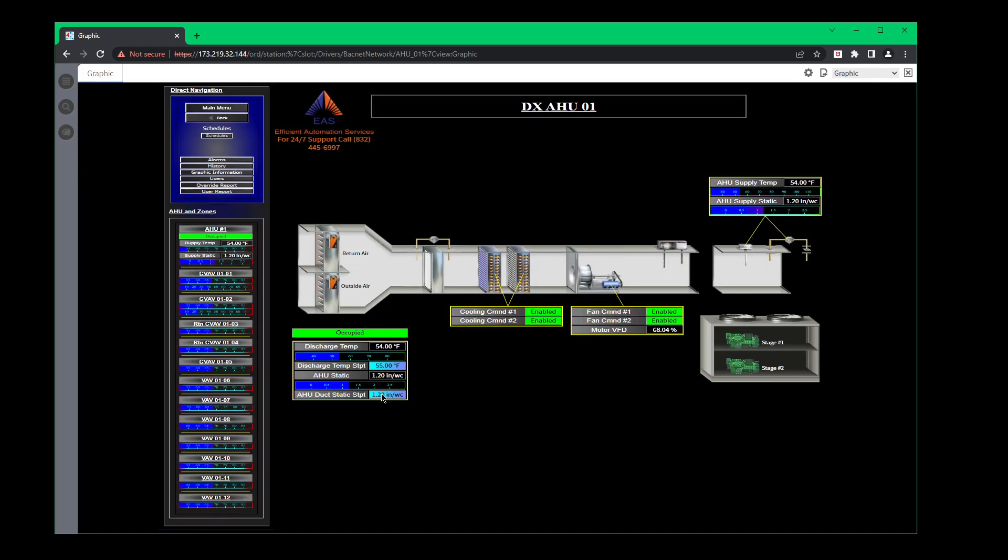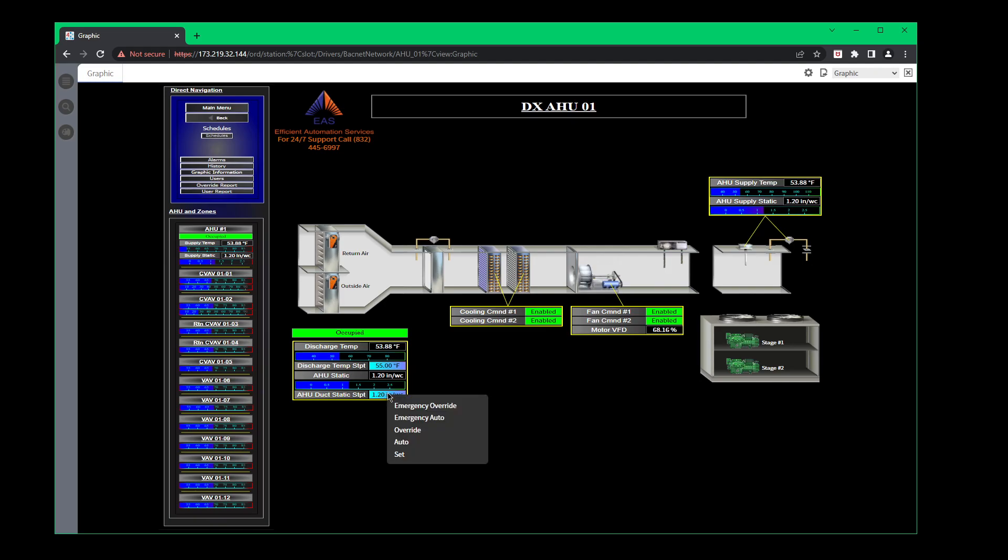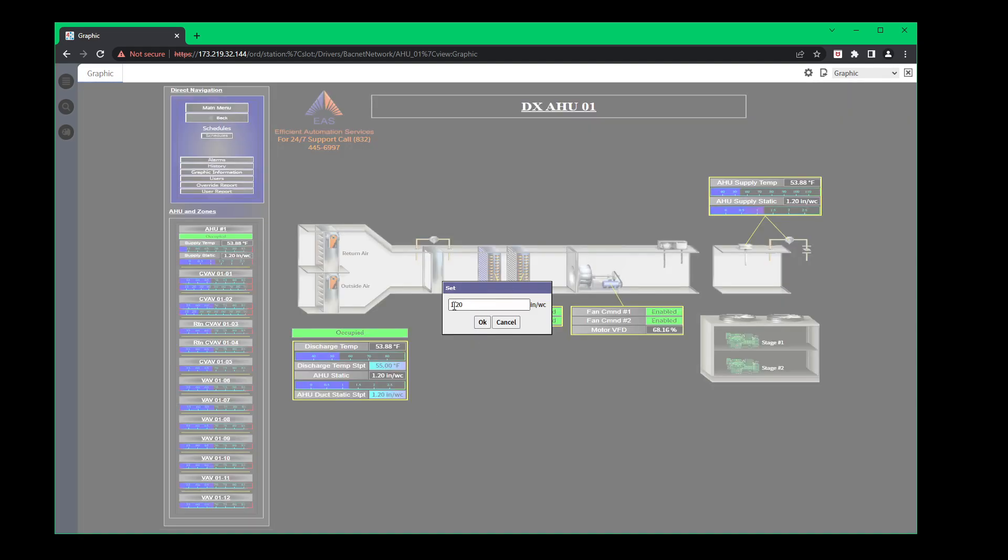Here's your duct static. Now if you ever see this duct static at .5 or anything less than 1 inch, then you have an issue going on with your fans. And in order to maintain proper cooling and air flow to all the boxes, this has to be at around 1.2 inches of static. Right here shows your motor command, showing that the motors are both enabled and the percentage that is telling it to run to maintain this 1.1, 1.2 inches of static. Do the same thing, go to set, you can make your adjustments as needed right here.